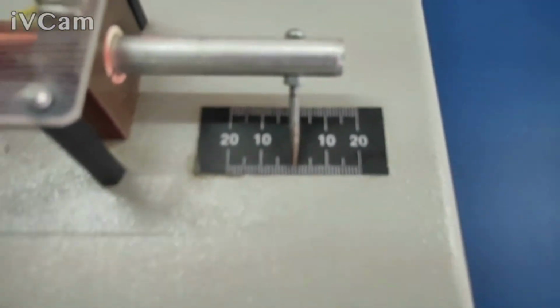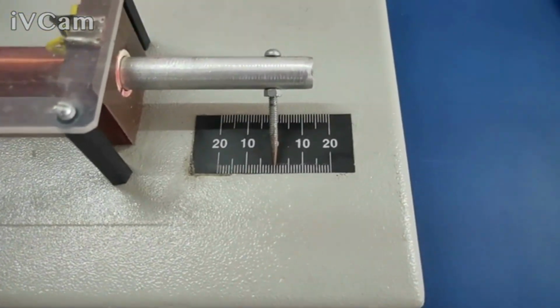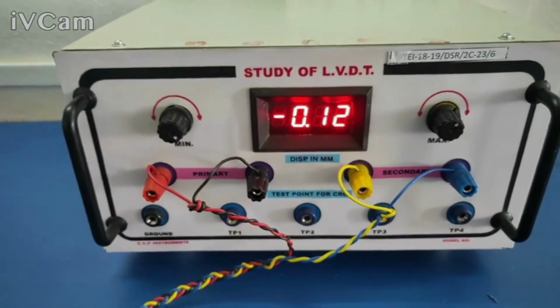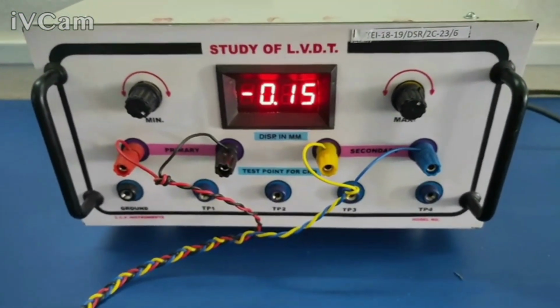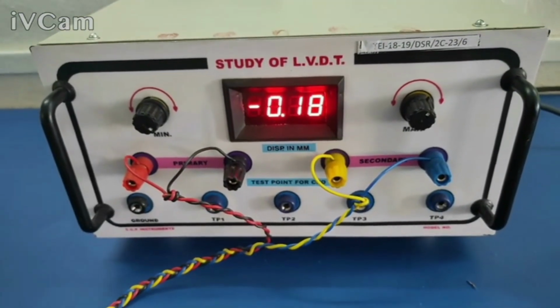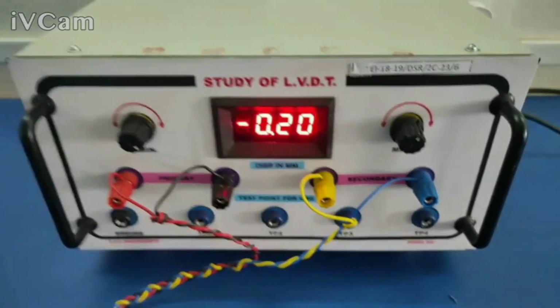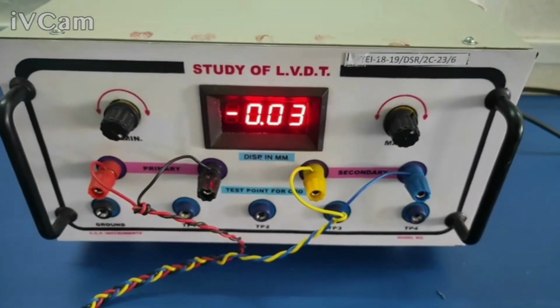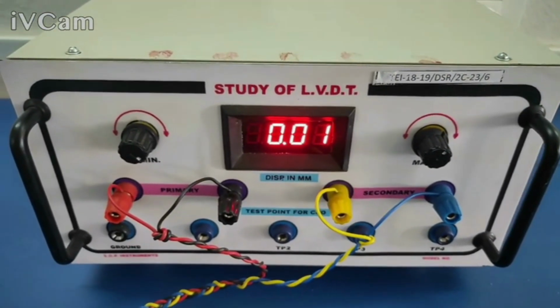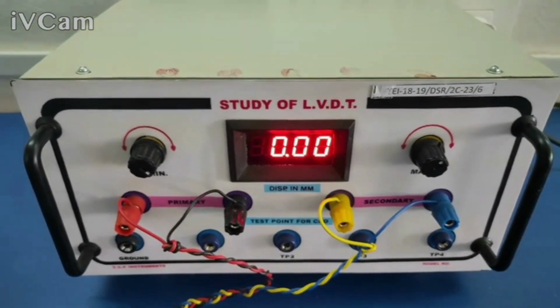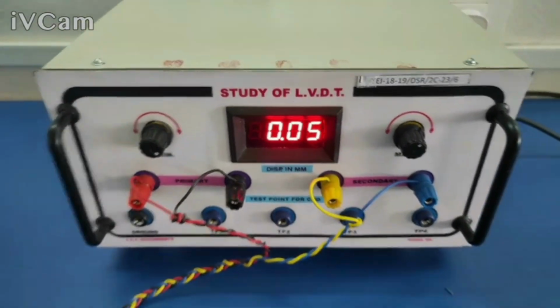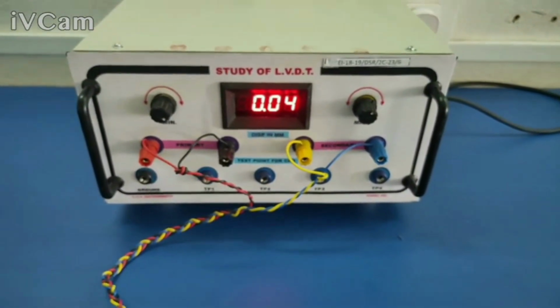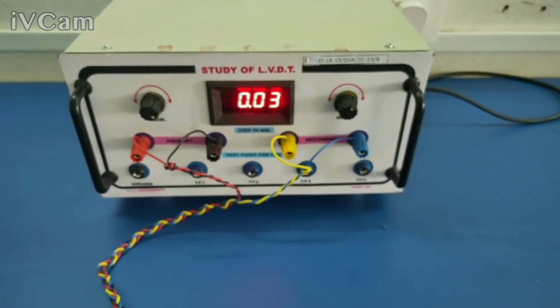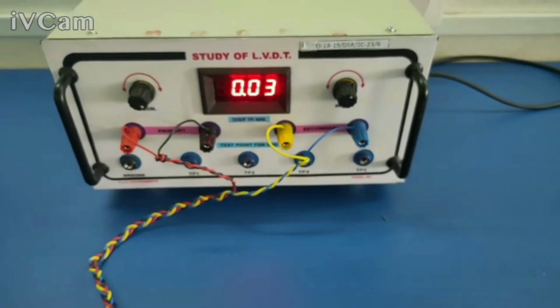So from the front, if you see, we have adjusted to 0 on the scale, and here, if you see, right now it is showing certainly a 0. It will fluctuate for a while, but we have to keep it in such a way. Now it is becoming 0. Okay. So with a small error of 0.02, 0.03, it's okay.